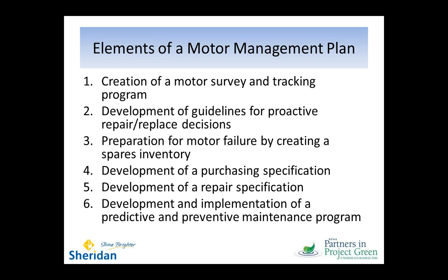The third principle I want to cover is the idea that you need to plan. Here's the deal with motors: they're tied into your processes. While I've now gone through a series of background slides that can tell you why motor selection is important and why it can make good savings, and really it can, the reality is that measuring and evaluating systems in place is tricky. When your key piece of equipment's down, that's really not the time you're going to begin evaluating whether you had the motor at the right size, or what kind of efficiency it had. What you're going to do is reach for the fastest thing you can find. Hopefully it's the right one.